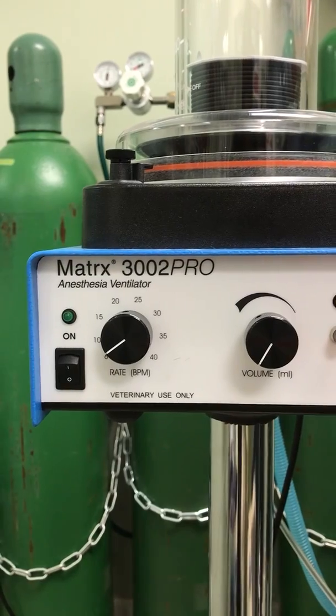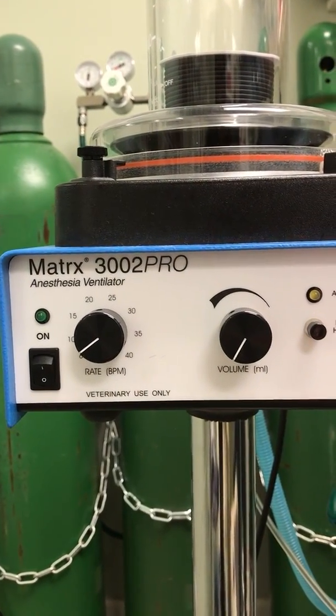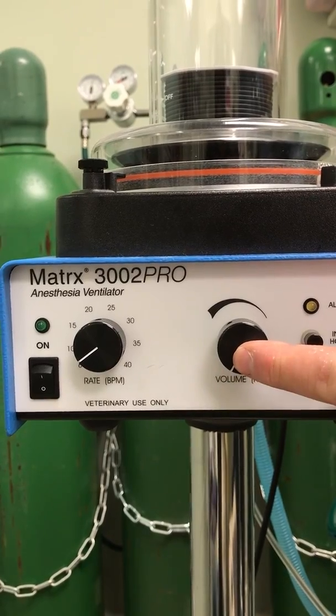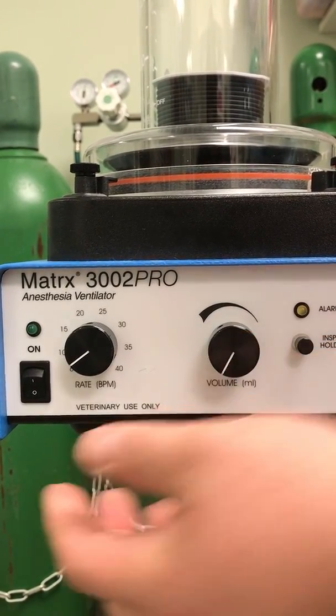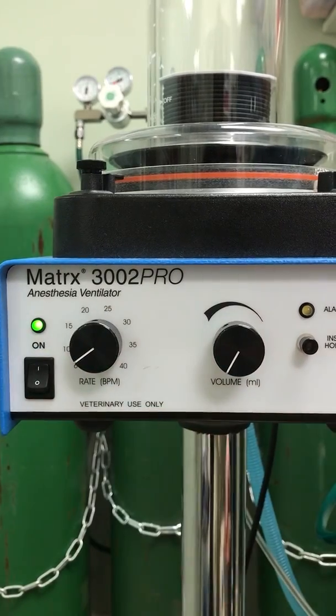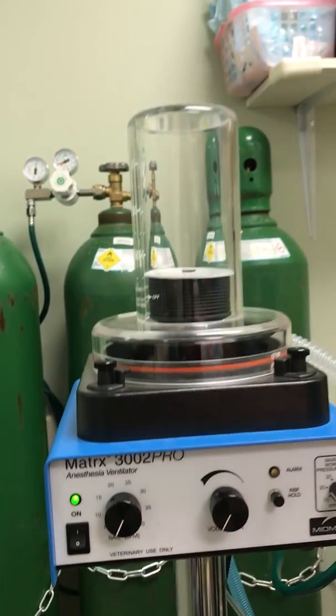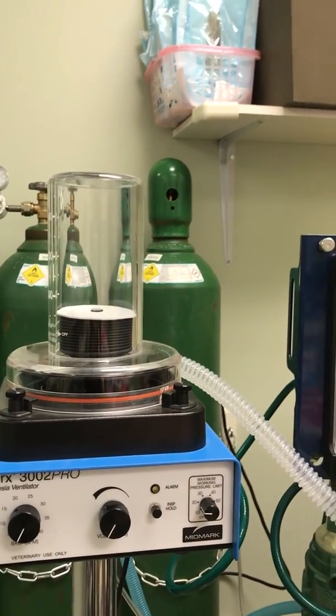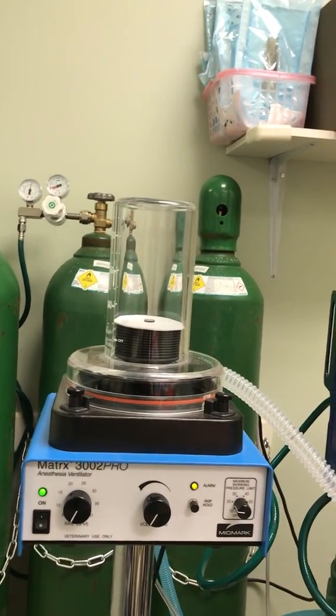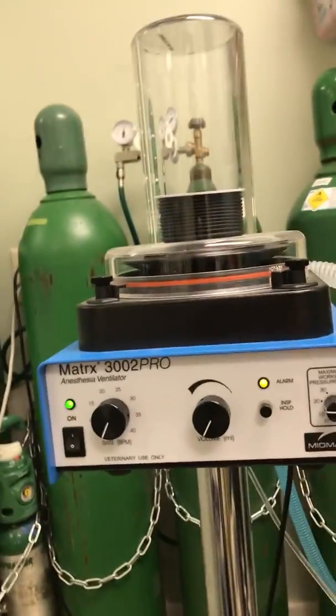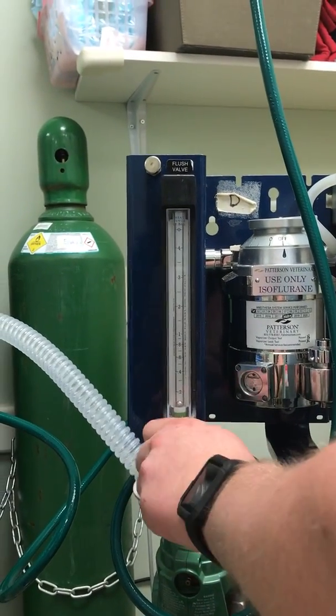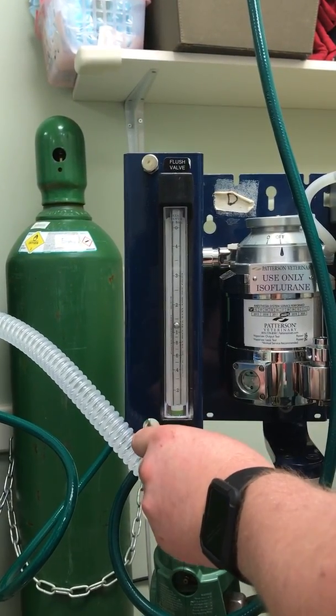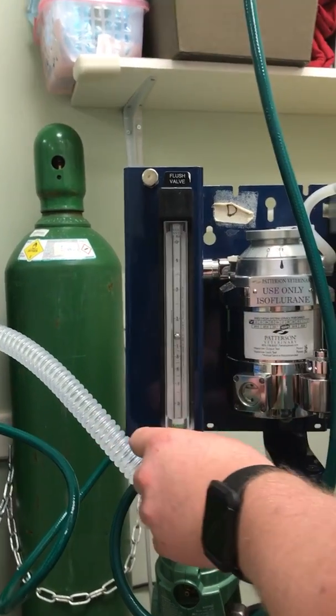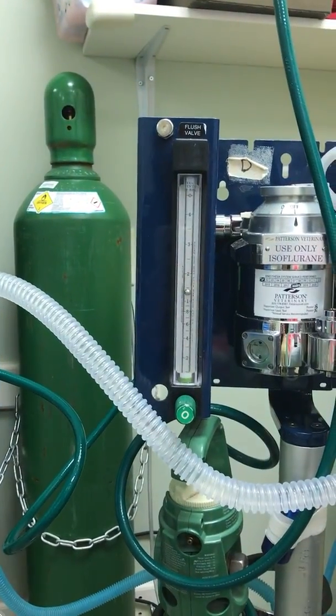And then we're going to hear some alarms when we turn this on, because the minimum pressure on this machine will be like less than 5. We have no flow, so there's going to be no pressure buildup. So there will be an alarm. Okay, so this is telling us we don't have enough oxygen going through the system. So we're going to turn our oxygen on our anesthesia machine. Right now we'll do about 1. Adjust that for your size of patient.